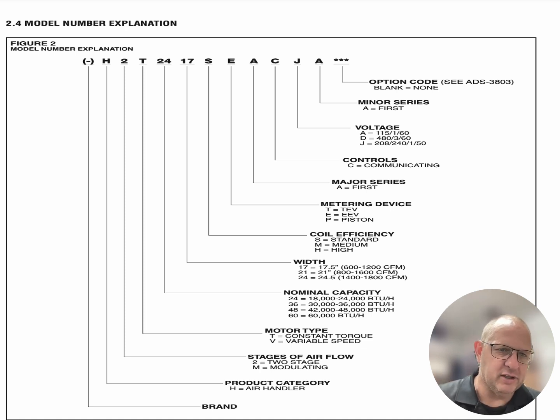So we look at the brand, it will tell us the brand, and they'll put that on there when we are buying the piece of equipment. We know that the product category is an H. We see that right here. It's an H that tells us an air handler. It's a 2, and if I come down to the stages of airflow, it tells me that there are 2 stages of airflow for this particular unit. The T has to do with the motor type, which is an ECM type of motor, constant torque, and not a variable speed ECM. The nominal capacity happens to be a 2-ton, 17-inch cabinet with an EEV, or an electronic expansion valve on there. And we're going to gain all that information from that model number itself. So it's very important to look at it.